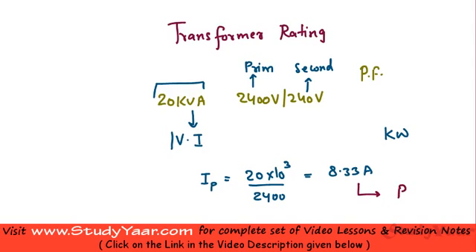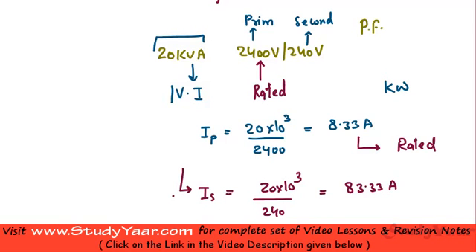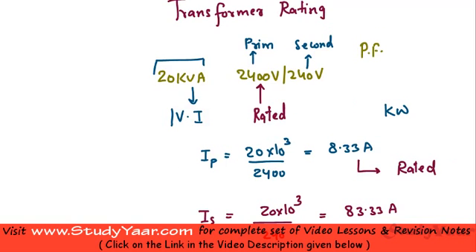Just like these quantities are known as your rated voltages, you can find out the maximum allowed current. Similarly, the maximum allowed current in your secondary would be 20 × 10³ divided by 240, which is going to be around 83.33 amperes. That's the rated current allowed to flow through your secondary. If you use any value higher than this, you are basically reducing the life of your transformer. These are the maximum safe values that you can use.